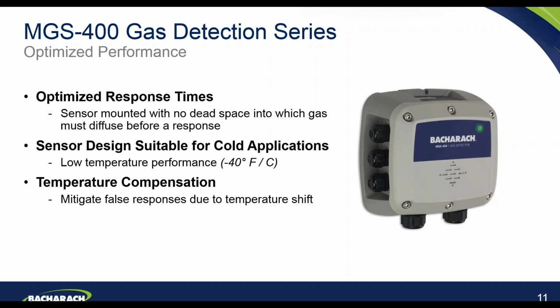In addition, and this is a very critical point that we identified as perhaps not being met by some parts of the market, it's important that the detectors are suitable for low temperature performance. Each of the MGS-400 series gas detectors is certified down to -40. So it's suitable across a broad range of installation requirements, from ambient to cold stores right down to blast freezers. It can be a standardized solution across all of those areas.